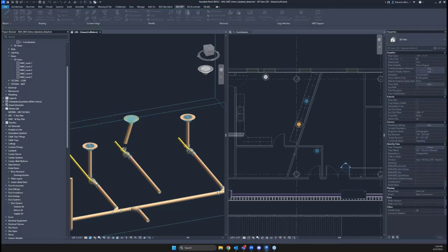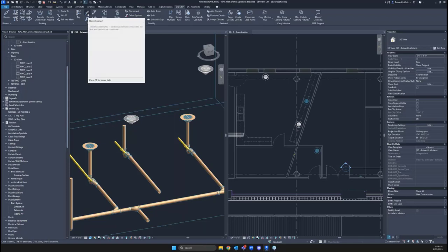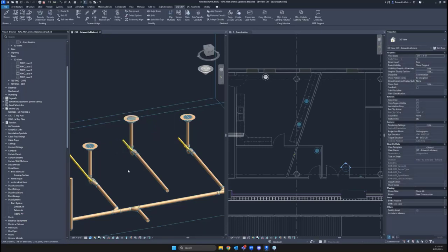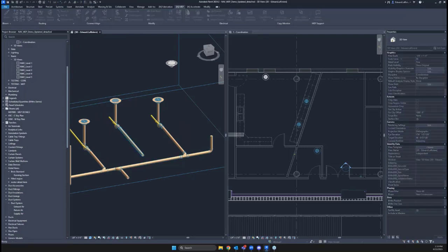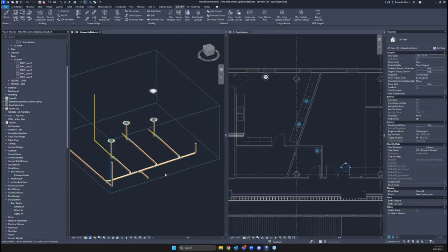Revit doesn't allow that to happen, which is why we created a very nice move connect tool that lets us choose a stationary, then a moving object. It'll maintain those relationships for the rest to just move it over and connect into place. From here, we use that exact same align branch tool to go stationary, then moving, fine tuning that connection, and then trim extend to connect it together, which that time I used a keyboard shortcut for.